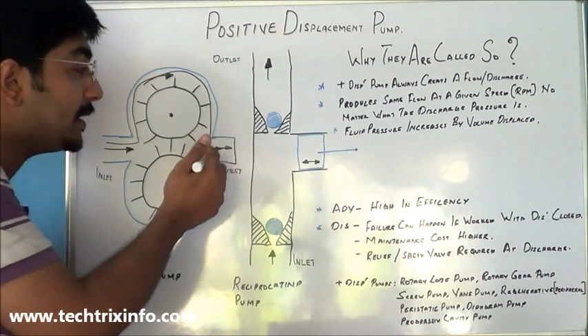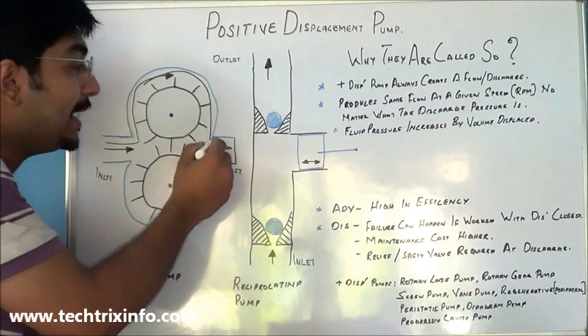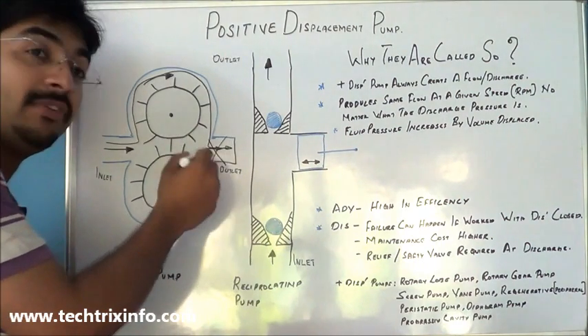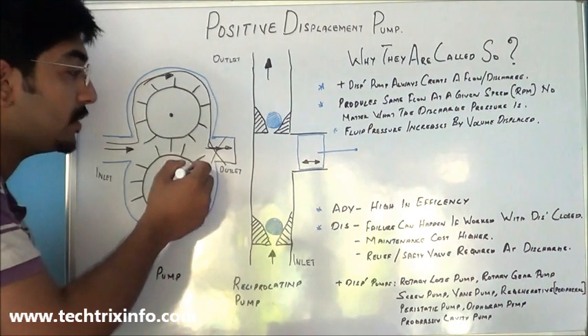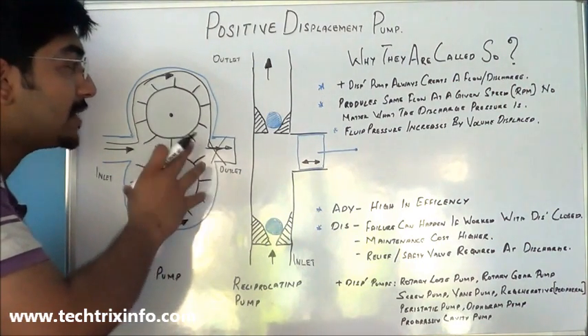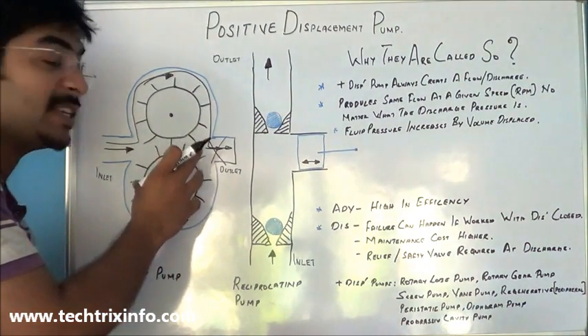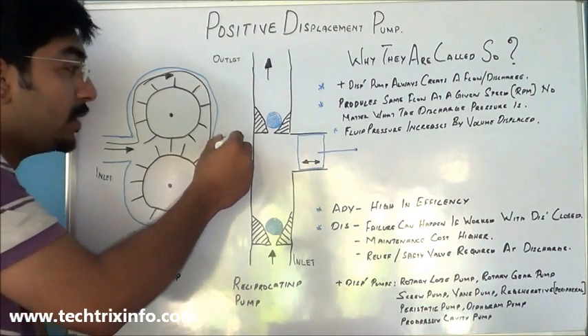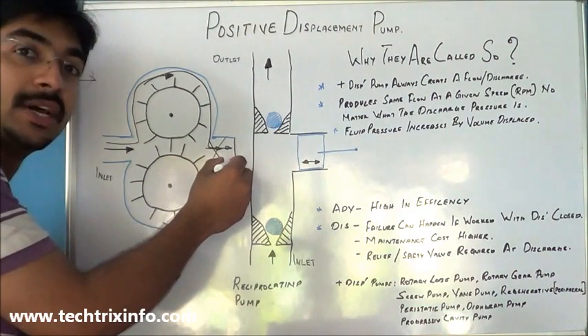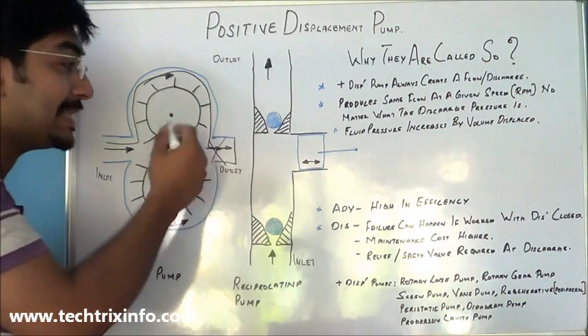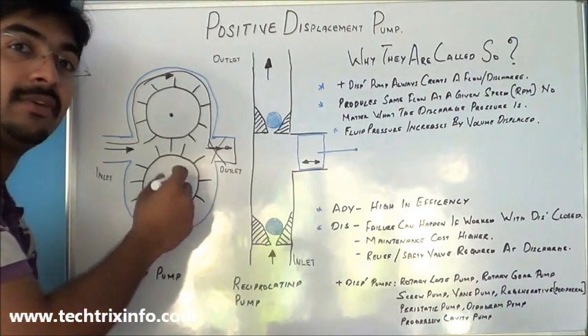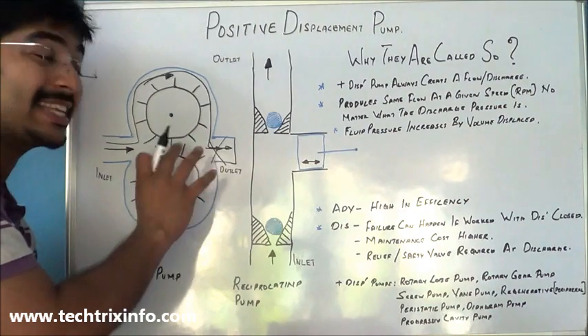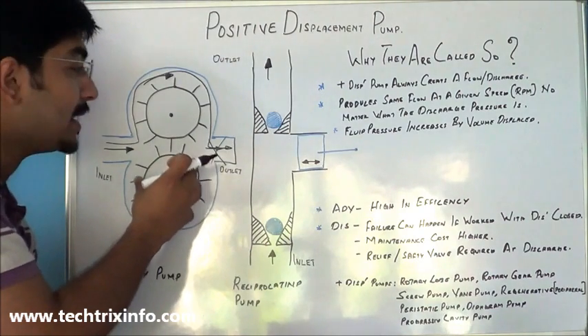As the pressure develops further, it will result in the mechanical failure of this pump. That's why a positive displacement pump can never work with a closed discharge unless it has a relief valve or a safety valve inside it.